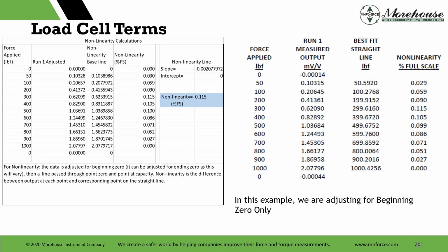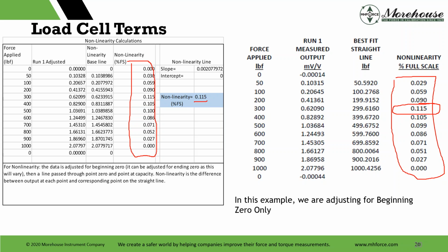When we look at this, here's what we have over here. Here's what we have on the certificate. And when I go over here in Excel, I can do this same thing again. And on the cert, we're going to say non-linearity. What we do is we find the maximum of all the points and we report it. And if someone's astute here, they'll say 0.030029. There's just a slight bit of rounding going on there. But if we look at what's on the certificate, it's 0.115% of full scale. So we basically fit the data to a straight line right here. Non-linearity baseline, fit the data from the straight line, and then we take the difference. We take the difference between the adjusted run and the straight line, and we report that.